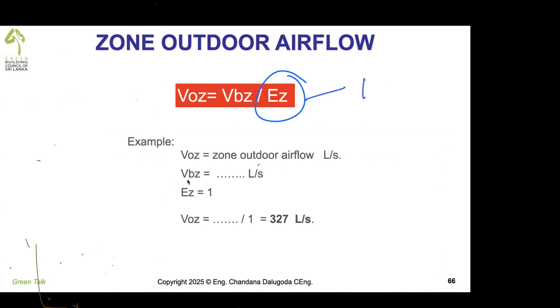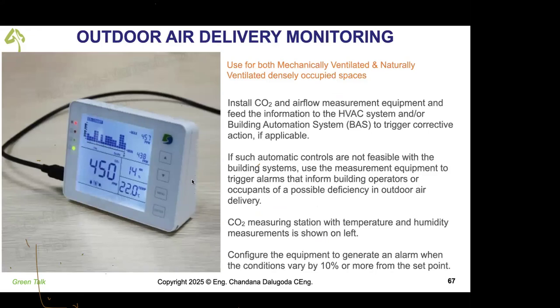So it is the normal calculation VBZ. How you do that? Number of people into a rate per person plus area into rate per area. You get the liters per second. That will have to provide. That's how we comply ASHRAE 62.1. Outdoor air delivery monitoring. We'll have to use special CO2 sensors, meters, and this is coupled with the BMS. If you don't have a BMS, this has to couple with a buzzer. If CO2 levels are going up, then we can open windows, doors for a short period to get the CO2 level down.